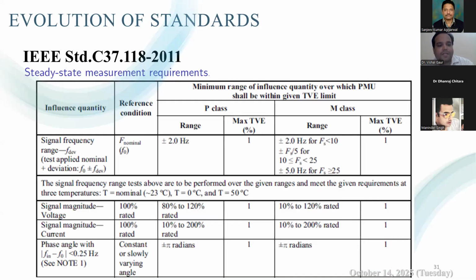Now let us see how PMUs are tested under different influence quantities like frequency variation, voltage and current range, etc. The IEEE sets the limit on how much error a PMU can have under the standard test conditions, and the error is measured in terms of total vector error. So here you can see this particular standard defines this total vector error limit for both the classes, P class and M class, for different influence quantities like signal frequency deviation, voltage and current range, and phase angle.